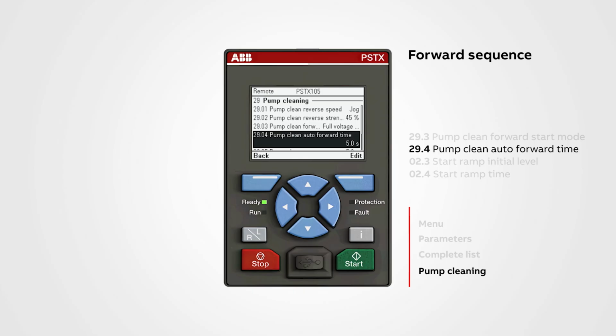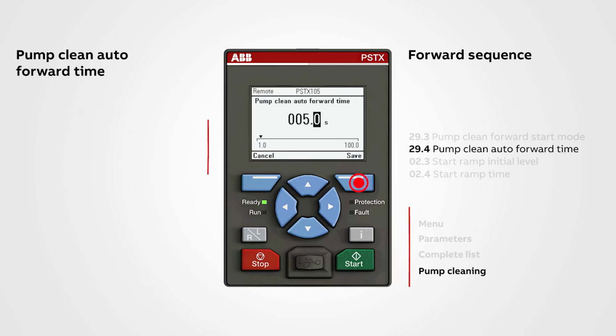Next is the 29.4, pump clean auto forward time. This parameter sets the number of seconds to run the motor forward for one cleaning sequence for the automatic pump cleaning. The range of this setting is between 1 to 100 seconds. The default value is 5 seconds.